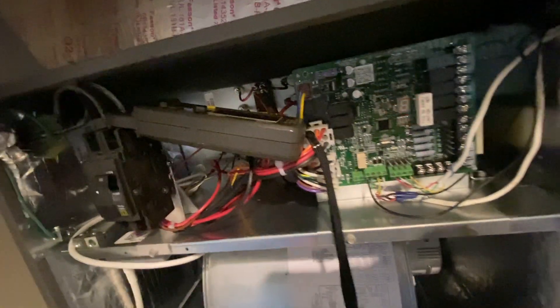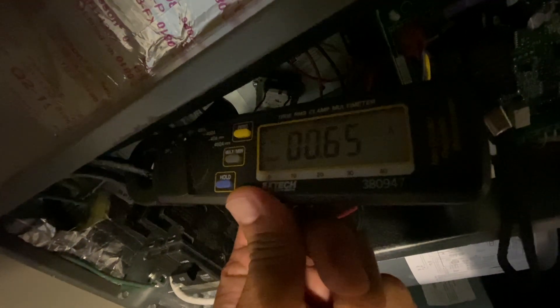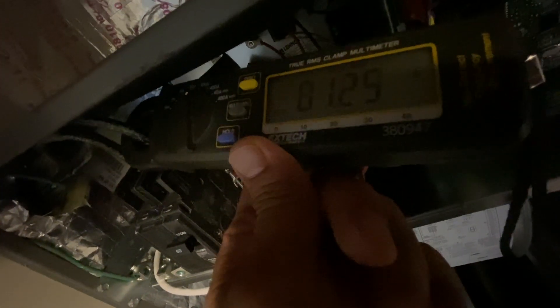I'm going to go ahead and turn the system on at full capacity — it should be running at maximum rate. It's a variable speed so it takes a while to come on and catch up to speed. You can see the amps are creeping up a little bit — you can probably hear the blower motor speed as well.